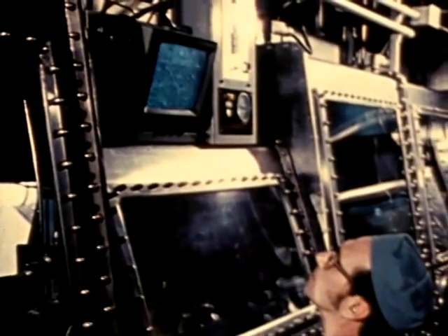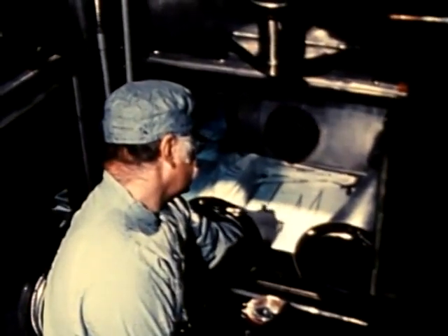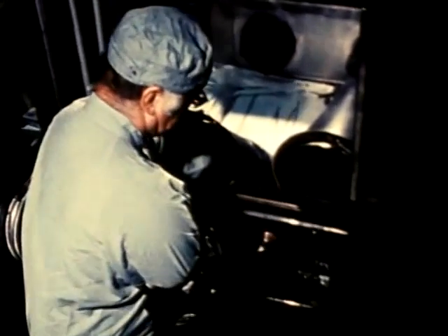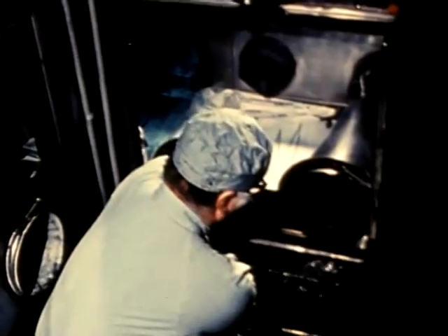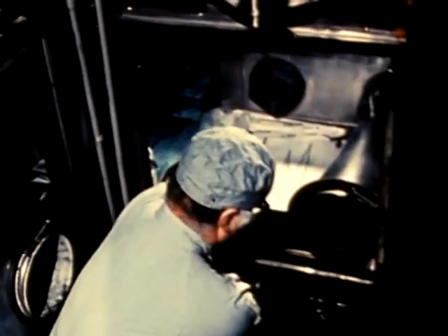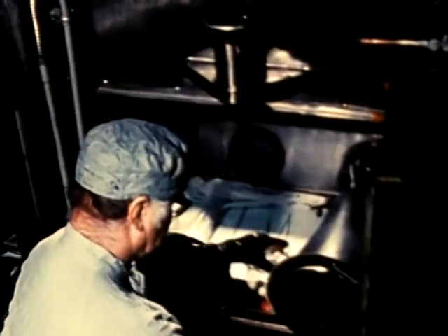The second means of entering the enclosed cabinet line is through a device called a dunk tank. This consists of a tank filled with a strong liquid disinfectant and is an integral part of the barrier. Like the autoclave, it prevents the passage of unwanted living organisms in either direction. A leak-proof container is used to convey materials needed inside the line safely through the dunk tank.